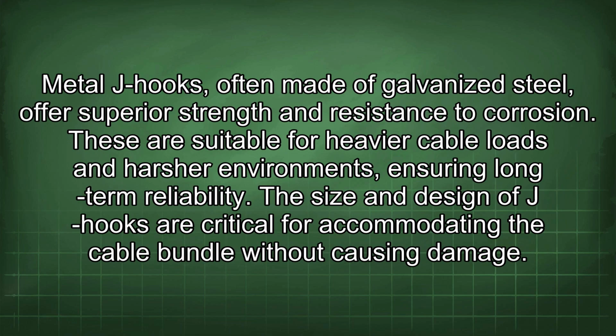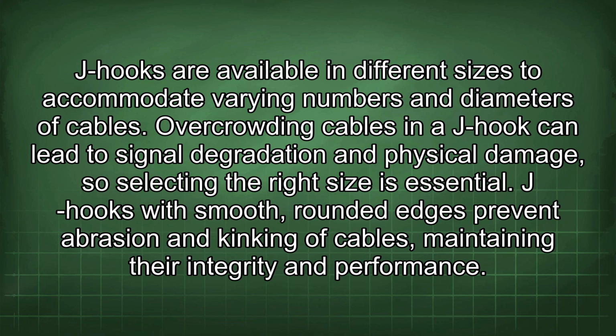Metal J-hooks, often made of galvanized steel, offer superior strength and resistance to corrosion. These are suitable for heavier cable loads and harsher environments, ensuring long-term reliability. The size and design of J-hooks are critical for accommodating the cable bundle without causing damage. J-hooks are available in different sizes to accommodate varying numbers and diameters of cables. Overcrowding cables in a J-hook can lead to signal degradation and physical damage, so selecting the right size is essential. J-hooks with smooth, rounded edges prevent abrasion and kinking of cables, maintaining their integrity and performance.